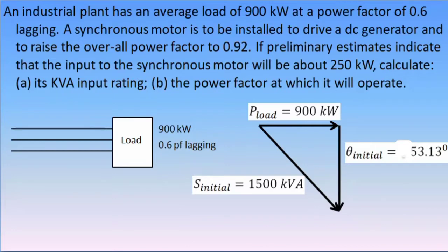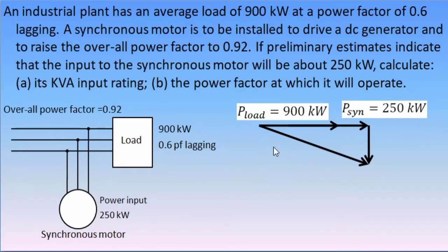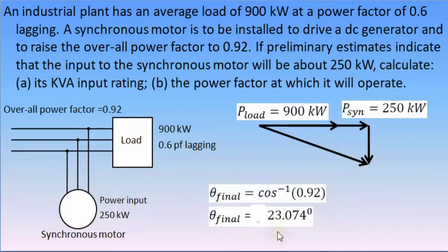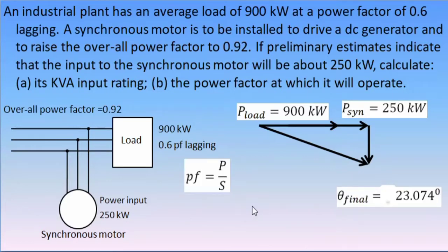Now let's take a look at the final Phasor diagram when the synchronous motor is being installed. The effective powers consumed by the load and the synchronous motor are in phase at an angle of 0. The power factor is raised to 0.92. The power factor angle at this condition is the inverse cosine of 0.92. This is 23.074 degrees.